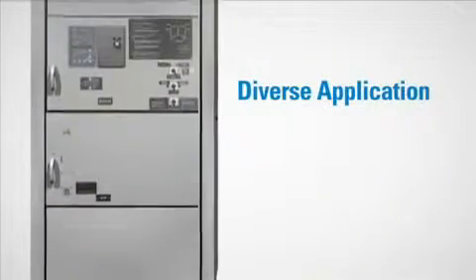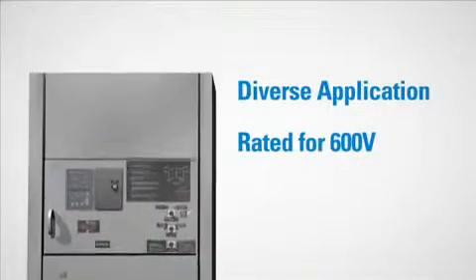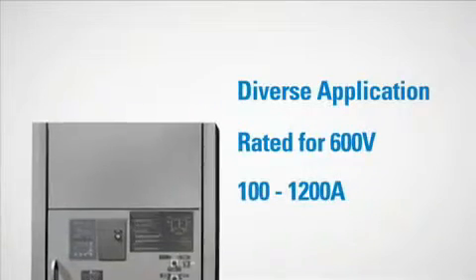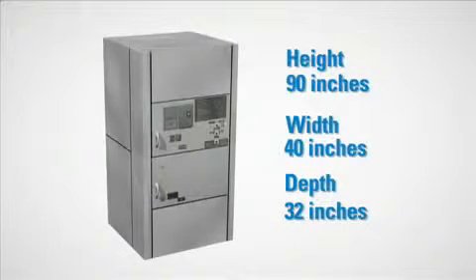The bypass isolation switch was constructed for use in a variety of applications. The unit is rated for 600 volts and ranges from 100 to 1200 amps. The structure itself is 90 inches high by 40 inches wide and 32 inches deep.